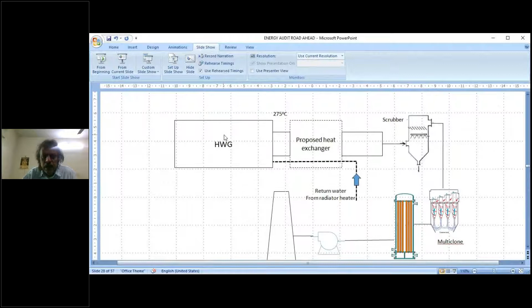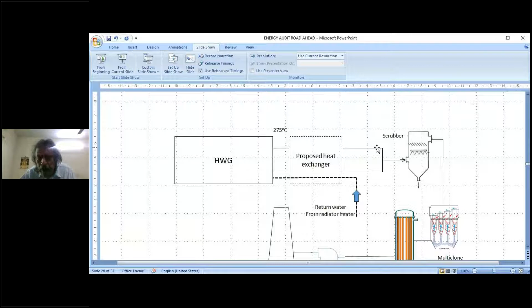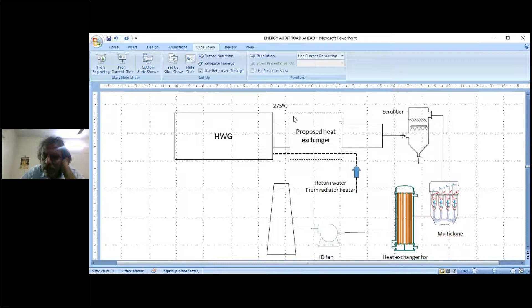And here also there is one hot water generator. This is similar to a boiler. So in some cases we find that there is still a lack of basic heat recovery systems. The temperature of what is going out here is 375 degrees, and we put a heat exchanger to recover. Heat recovery is one area where still a lot of potential lies. In this hot water generator, these are 275 degrees centigrade hot flue gases. So instead of going to the chimney unutilized, we put a heat exchanger and recover the heat.